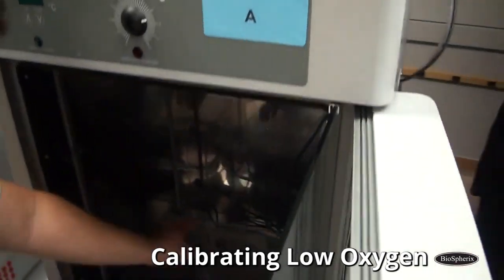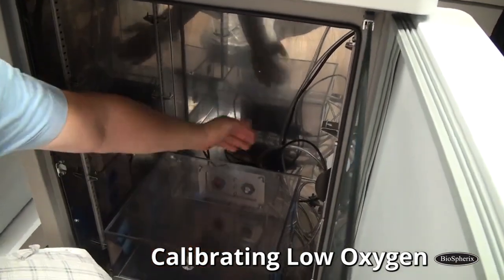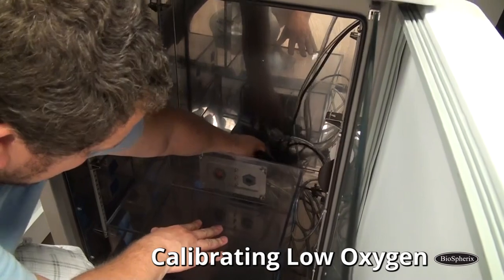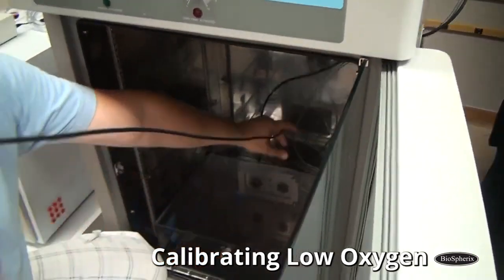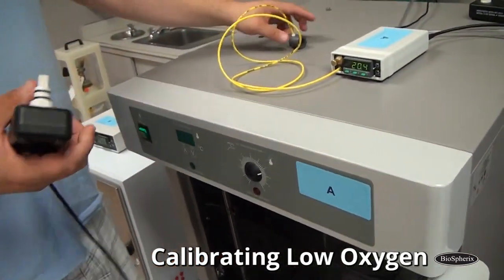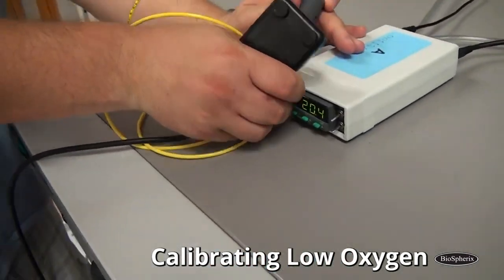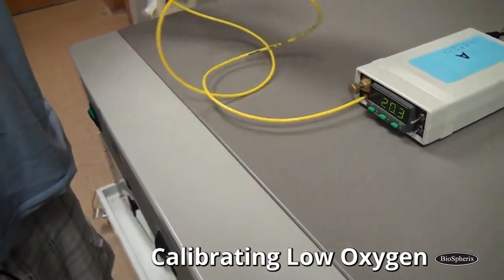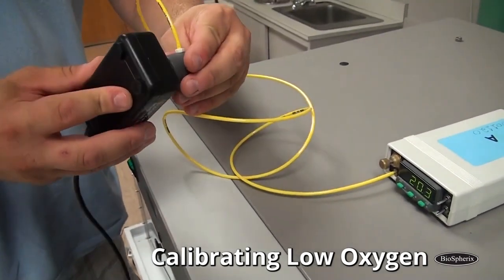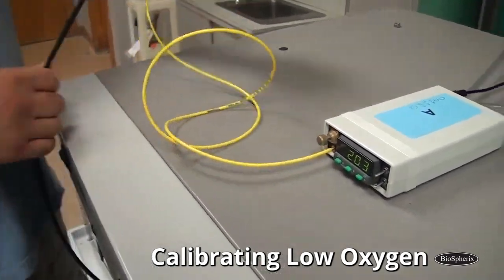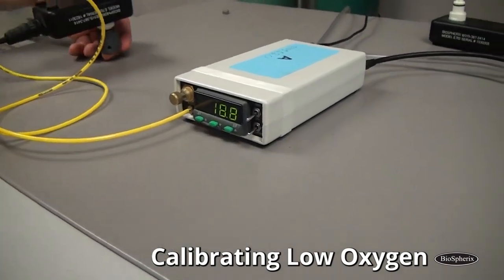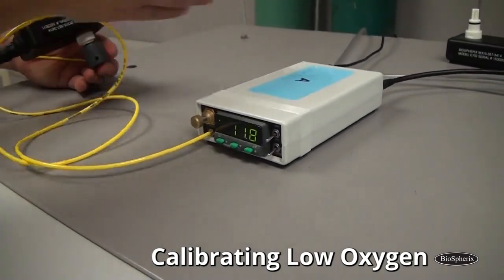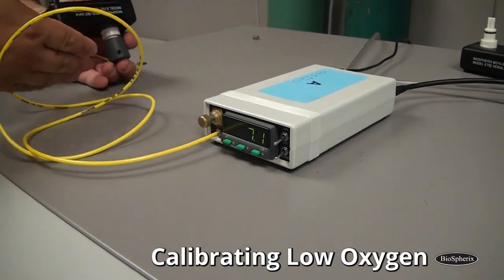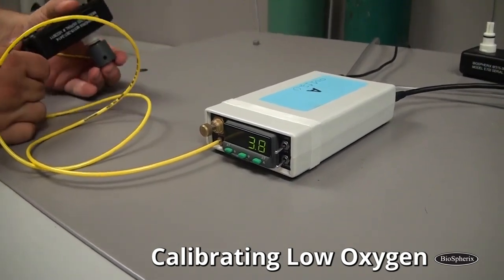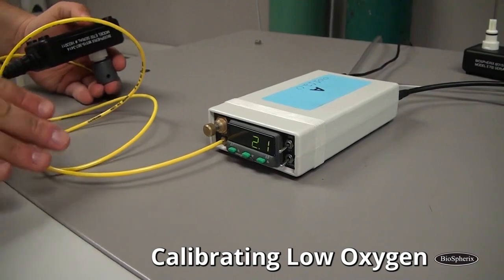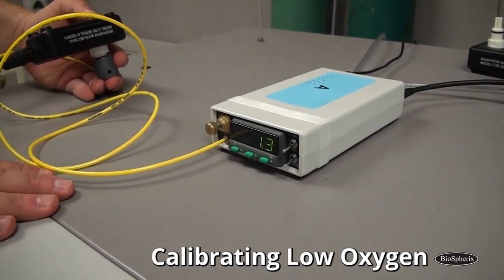I'm going to grab my sensor. So if this is your setup, I just pull the sensor out, pull it forward, and I'm going to put the tip right in there, and then I'm just going to watch the front of the controller. So this is our zero calibration. So what we're doing, we have nitrogen hooked up here. So pure nitrogen is flowing directly over to the sensor. So it should read 0.0.